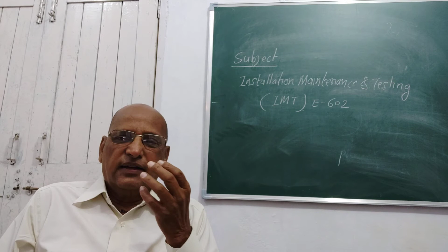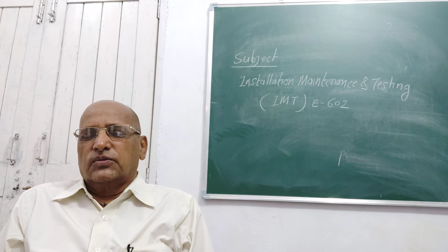As we know, there is a gap between rotor and stator. It varies from 1 mm to 3 mm. So very exact balancing of the rotor is to be done. Otherwise, when it starts running, there is a problem of friction between the stator and rotor, and it will damage the rotor and stator both. So we have to use a particular rotor balancing system for this, in which the rotor is properly balanced inside the stator after installation on the site.